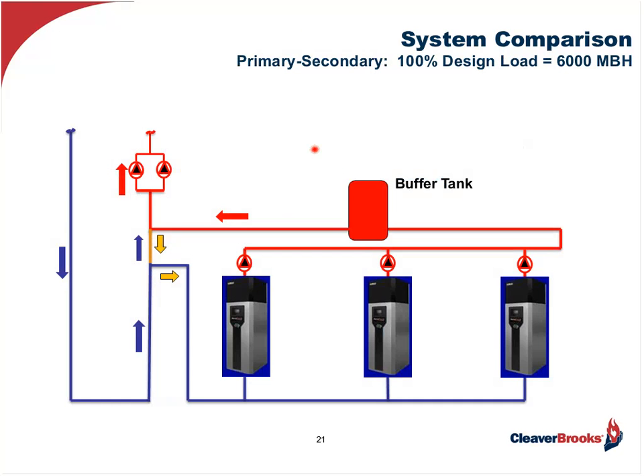Now, how do they compare? Here's a primary-secondary system. And by the way, one of the other takeaways is I'm going to be talking about low mass boilers here in this primary-secondary loop. You could do the same analysis with high mass boilers, and you would find the results to be very similar. So this is really going to be primary-secondary versus variable flow primary with high mass. Let's look at the system here, though.